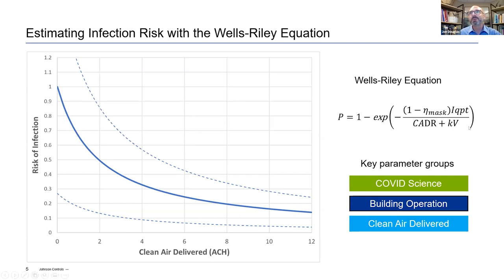There's a lot of parameters in this equation, but when you plot it in the most basic form, you get a risk curve that looks like the plot we have here. The vertical axis is a measure of the risk of infection, and the horizontal axis is the clean air delivered to the space. What you can see from this curve is that as you increase the amount of clean air delivered to the space, your risk of infection goes down pretty quickly. And I forgot to mention, the clean air axis here is air changes per hour. So we're talking about 4 air changes per hour or 10 air changes per hour.